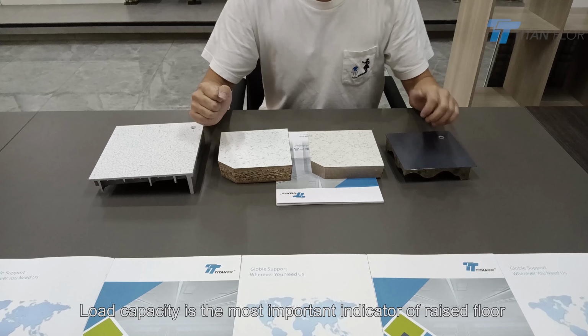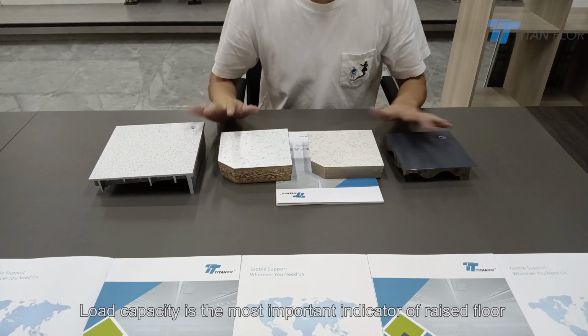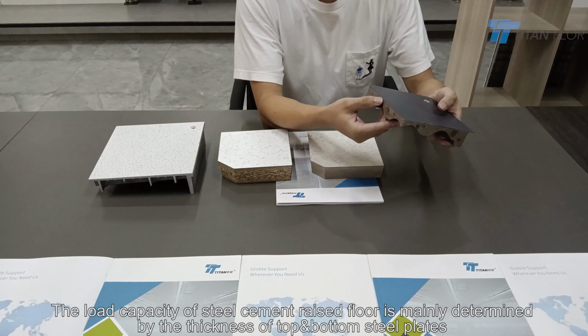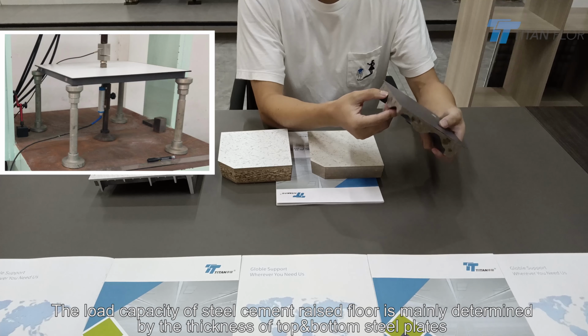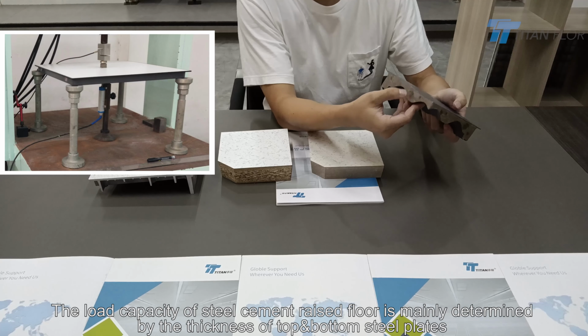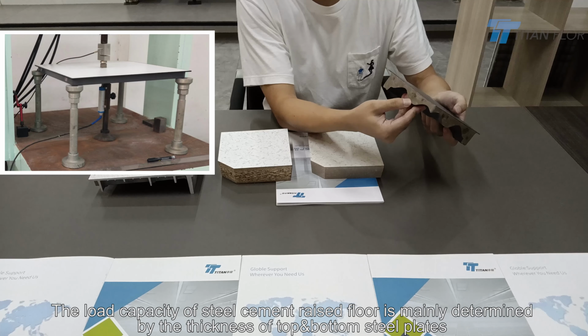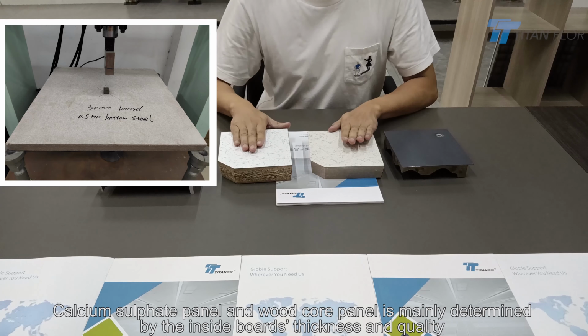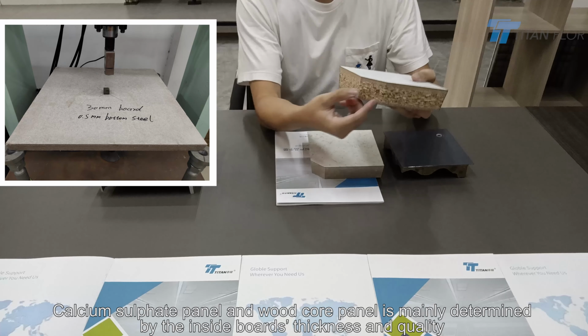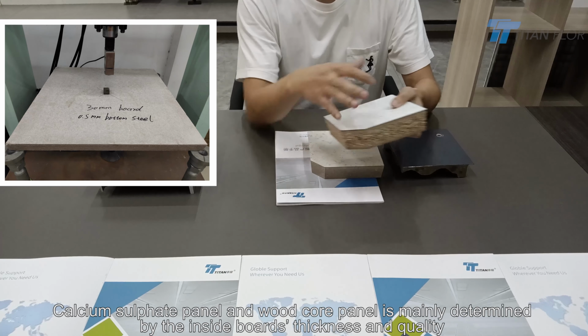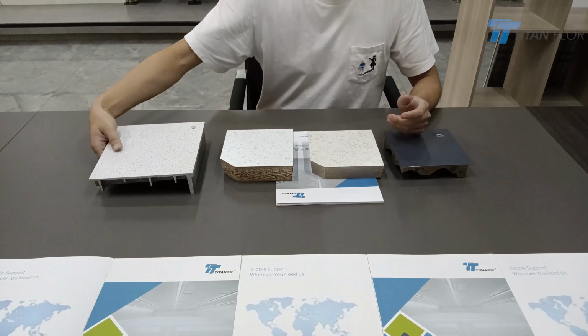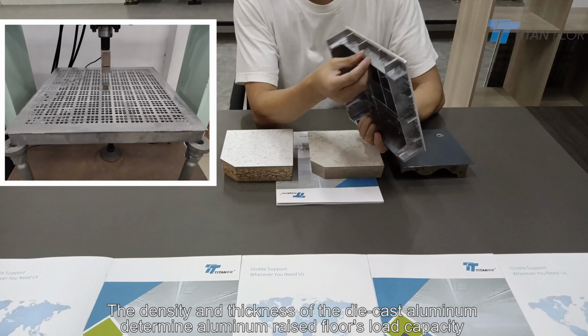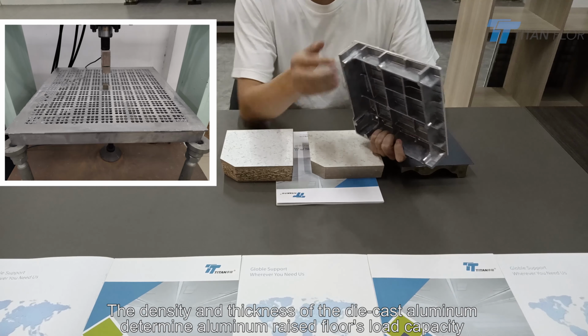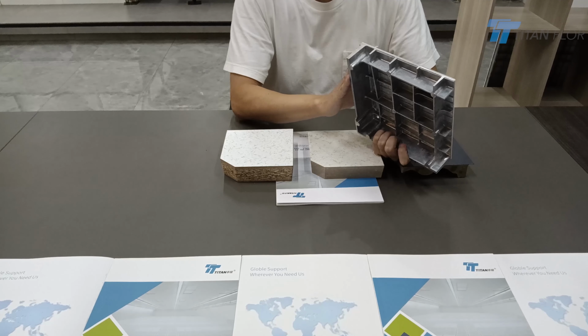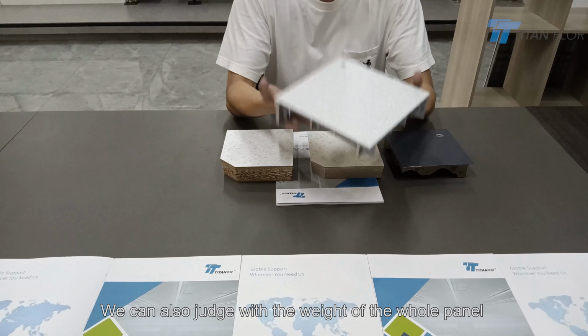Load capacity is the most important indicator of raised floor. The load capacity of steel cement raised floor is mainly determined by the thickness of the top and bottom steel plates. For calcium sulphate panel and wood core panel, it is mainly determined by the inside board's thickness and quality. The density and the thickness of die-cast aluminum determine aluminum raised floor's load capacity. We can also judge with the weight of the whole panel.